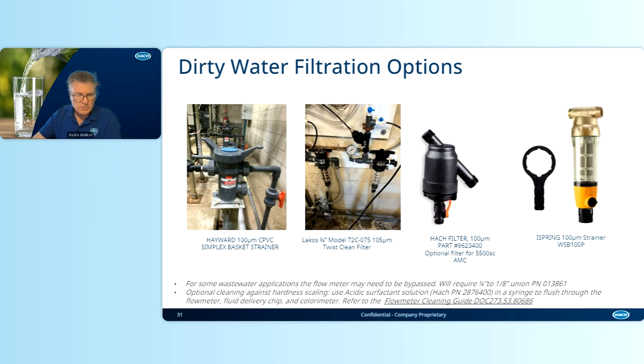So here are the options. Either Hach offers those options, or there are off-the-shelf options available for this filtration. What is common about these options? It's a 100 micron filtration, which usually sits after the 40 mesh strainer. The high capacity of this strainer or filter is absolutely advised here. You can see those options available through Grainger or even Home Depot sometimes. In the middle, you can see the Hach filter. Hach offers this filter for other applications and other instruments.